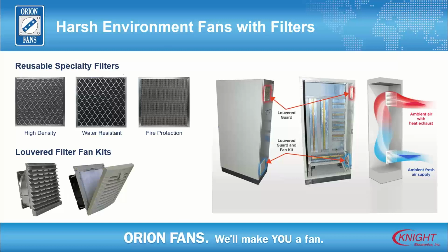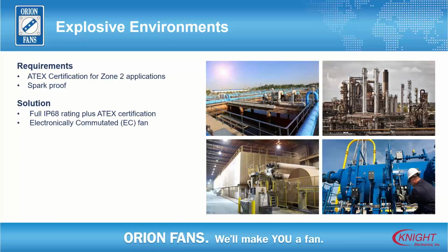Yeah. All right. So what special cooling requirements are there for explosive environments? Yeah, that's a whole other world. ATEX Zone 2. We are an ATEX Zone 2 application for our ATEX fan. We have a fairly small offering of that. It's 3 sizes currently. They are full ATEX rated. They are EC fans, which means they're electronically commutated. They're very efficient, and they have the ATEX certification. That's the big thing with them. ATEX means it's spark proof. That it should not cause an explosion.